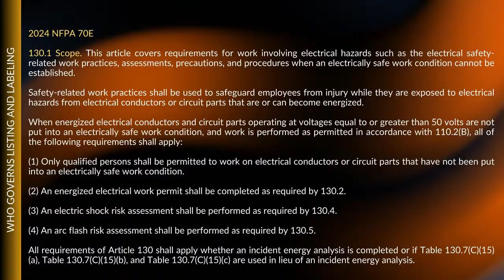It says, or greater, are not put in electrically safe work condition and work is performed as permitted according to 110.2B, all the following requirements shall apply. Well, naturally, you've got to be qualified, you've got to do a work permit, there's got to be an electrical shock risk assessment and an arc flash risk assessment.